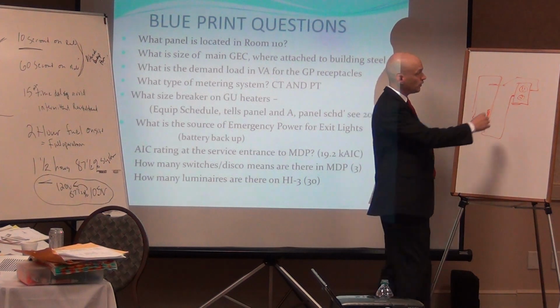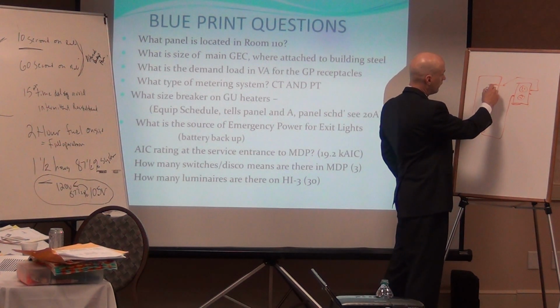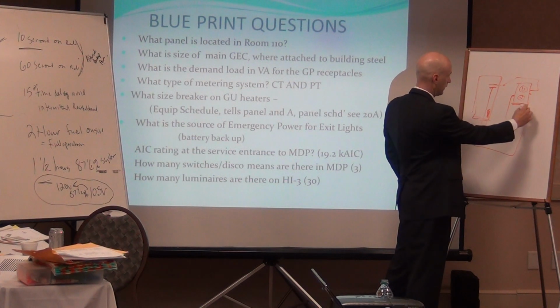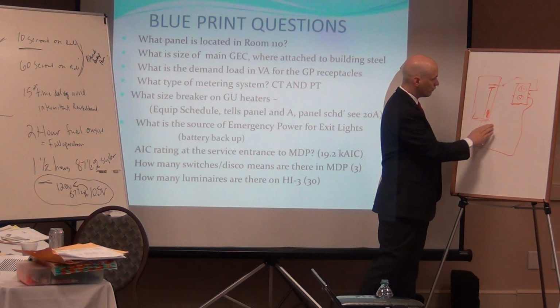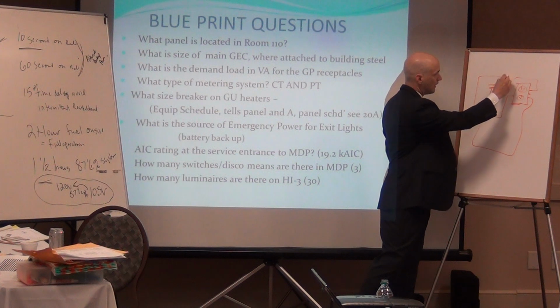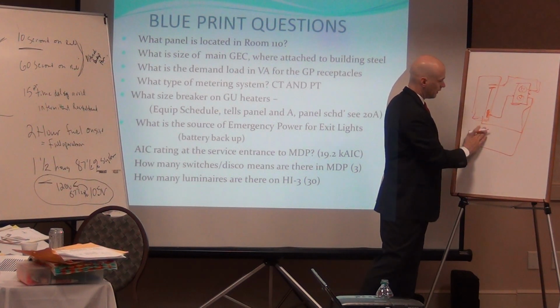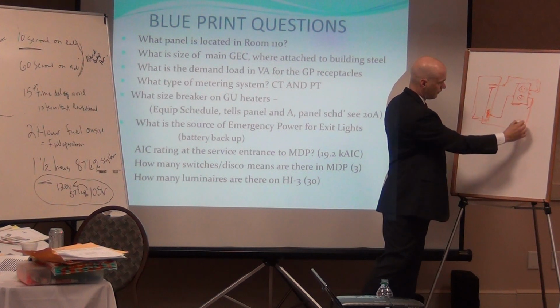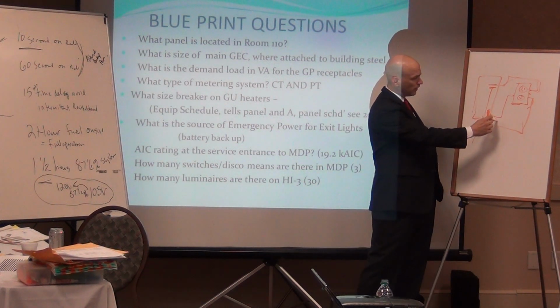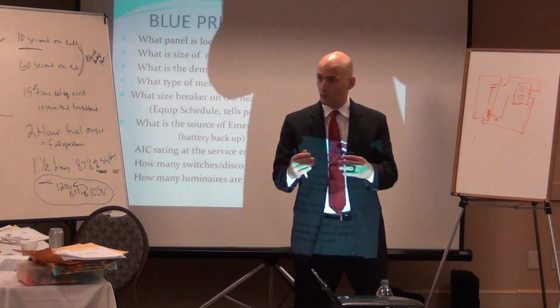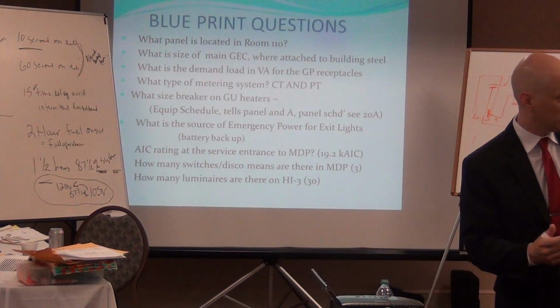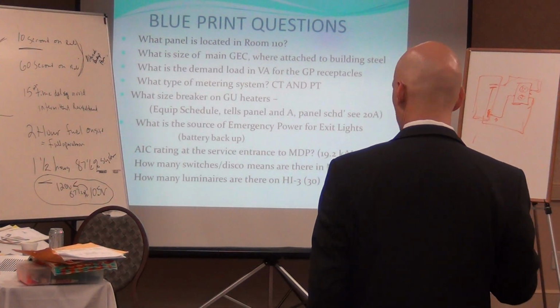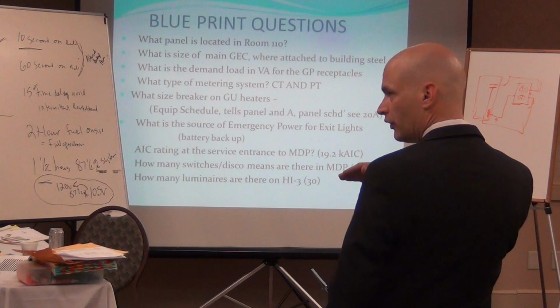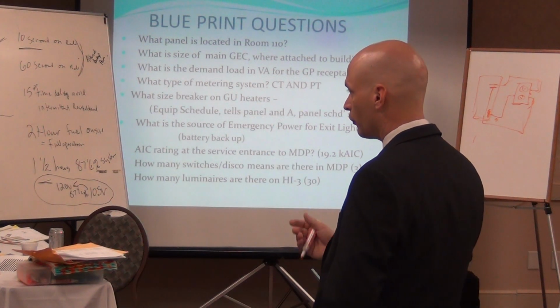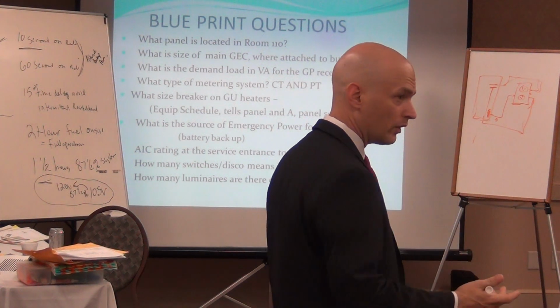as well. Now, if we split the tab on this side and bring another phase over here, and I'm just going to draw this over here like this, so they're kind of boxed in with that in the middle, then this wire becomes truly what is a neutral. So you've got A phase here and B phase here. I've drawn it to better scale so they look the same length and size. Because of the characteristics of the sine waves being the same shape, same waveform, when they meet in the middle, since both phases are directly opposed at 120 degrees, they cancel each other out, only to the point where they equal each other. And then anything that's left over is what's carried back on the neutral. So we call it carrying the unbalanced load, or the unbalanced portion.